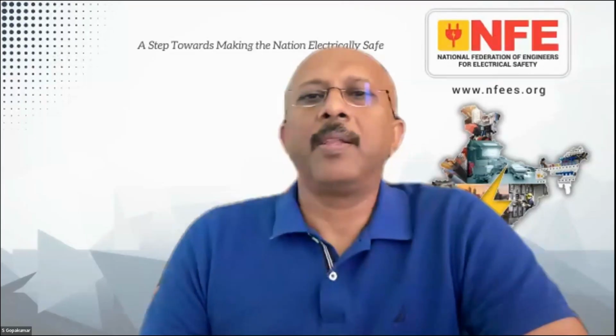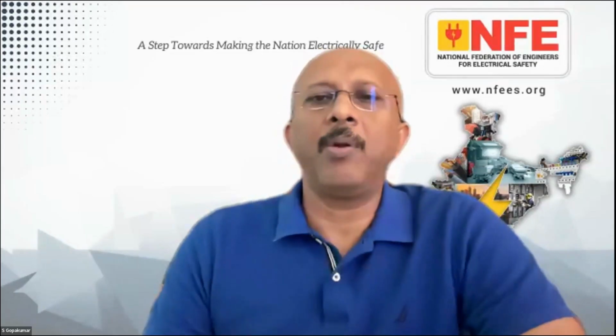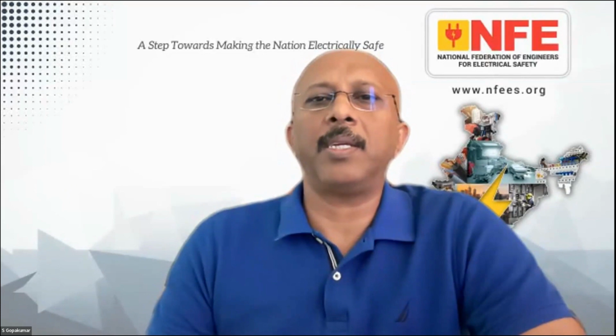So we need to assign a few hours or a day to perform all of these measurements and to make sure that we will be able to turn our network on and off, so energized and de-energized. But as it comes to fault loop measurements only, we perform them on the energized installations. Yeah, thank you. So it has to be carried out in energized condition.